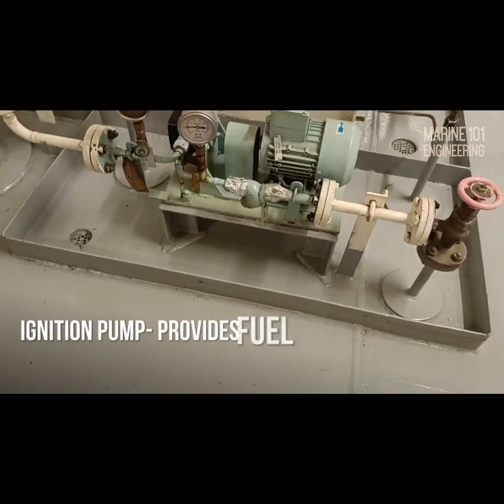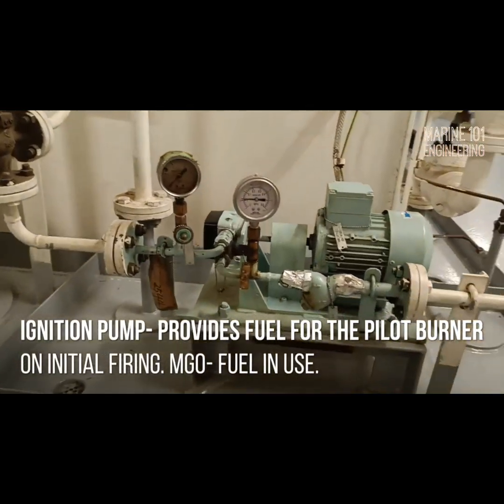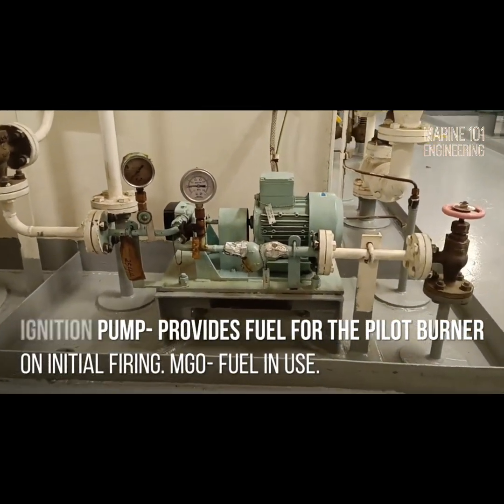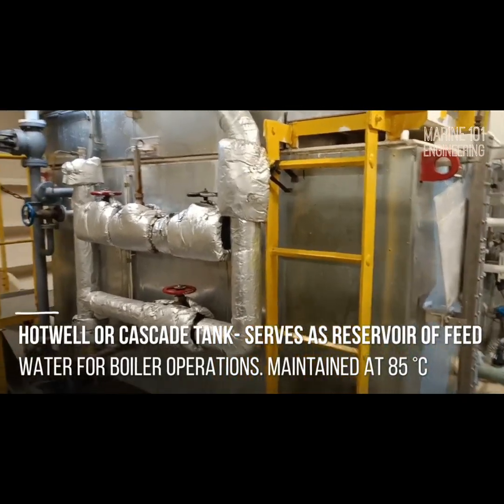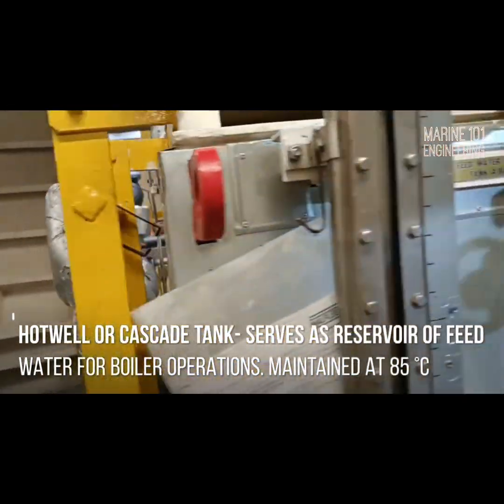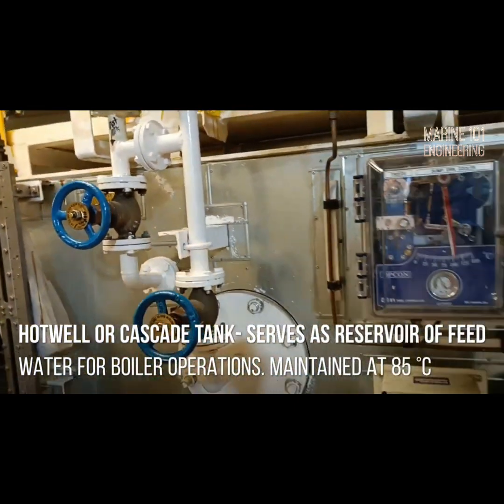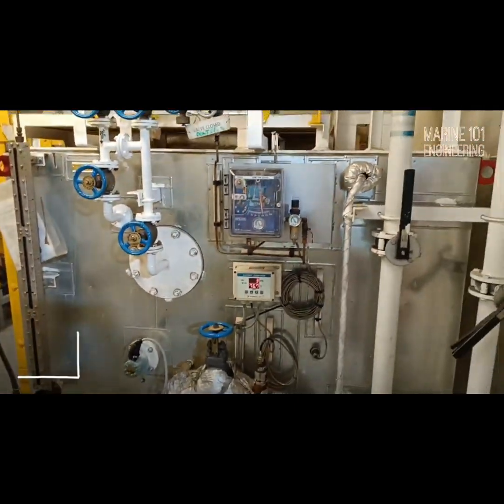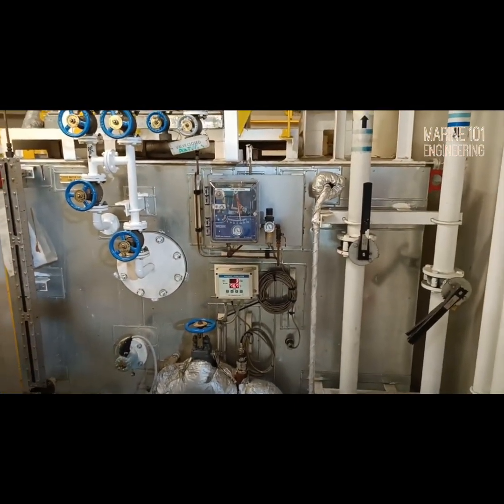First up, the ignition pump. The fuel ignition pump provides fuel supply for the pilot burner system. This unit uses marine diesel oil for pilot firing. Next, the hotwell or cascade tank serves as reservoir of feed water for the boiler water system. Ideally it should be maintained at 85 degrees Celsius.